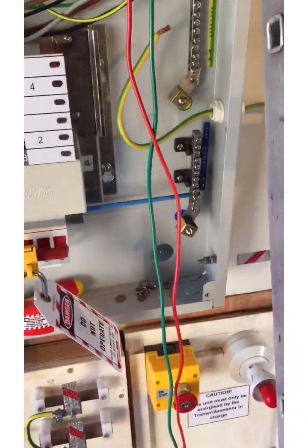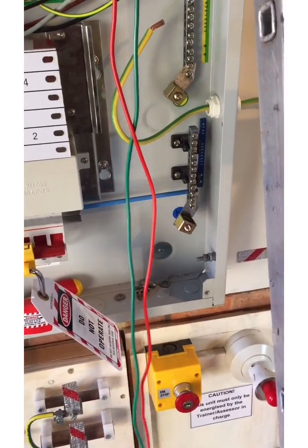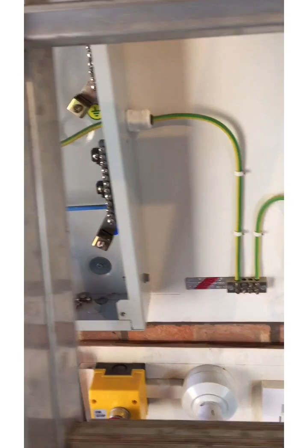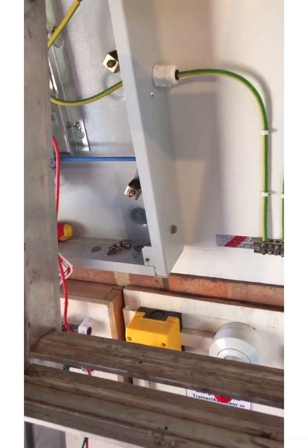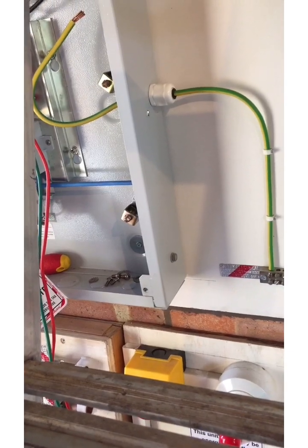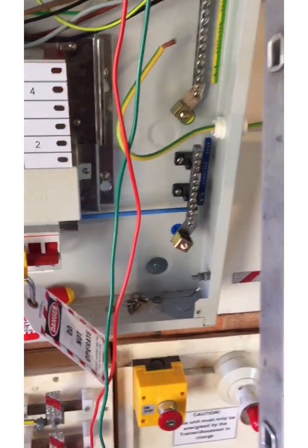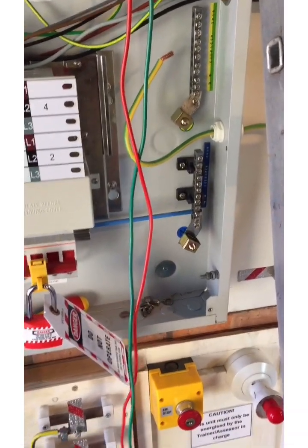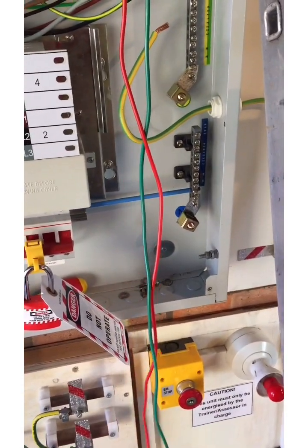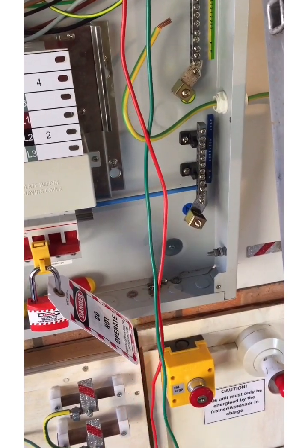Let's talk about the bonding. I've got the bonding disconnected here to avoid any parallel paths. In reality, if we can observe the bonding throughout its length, we wouldn't necessarily do a continuity of protective conductors test, but if that bonding disappears into a building void or there's any uncertainty about whether it's continuous, we would assess that with our R2 wander lead — I'll show you that in another clip.